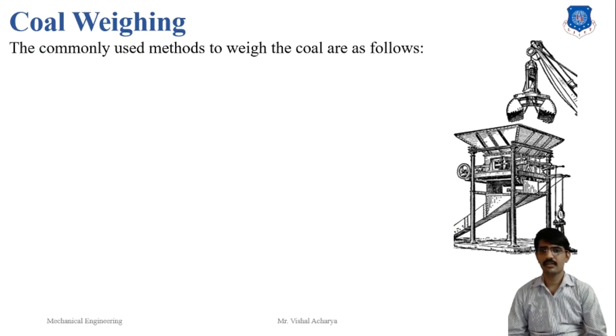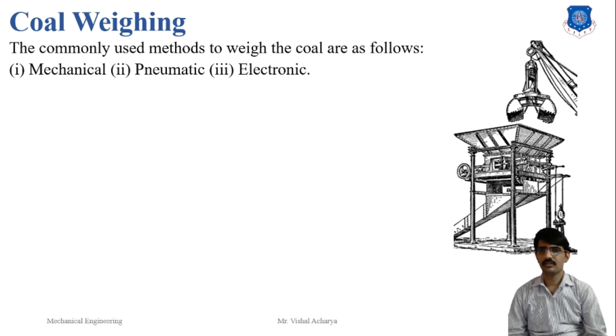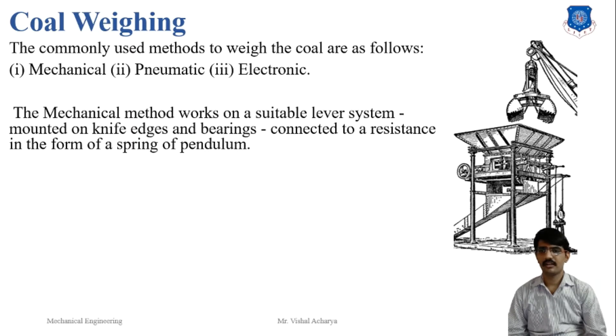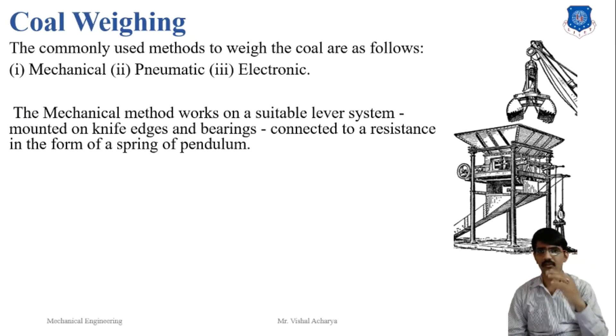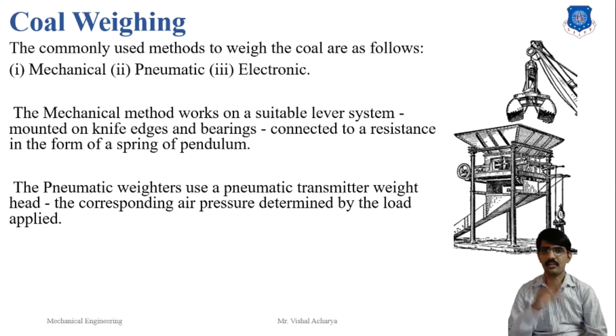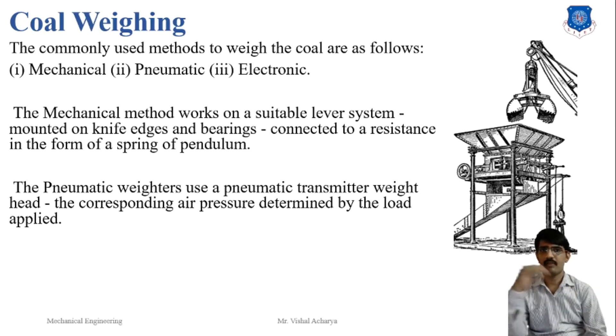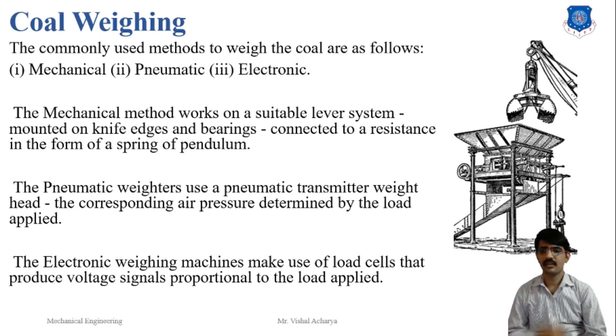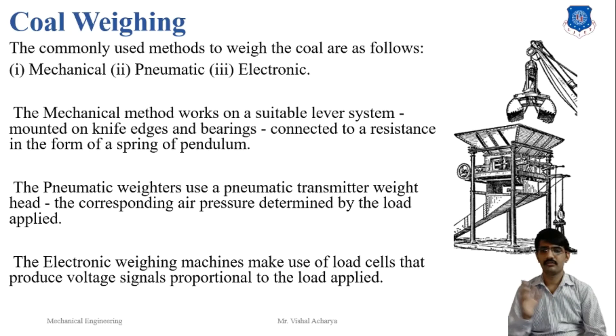Coal weighing is the commonly used method to check the quantity of coal before entering the boiler. Three systems are used: mechanical, pneumatic, and electronic. The mechanical method works on a suitable lever system mounted on knife edges and bearings, connected to a resistance in the form of a spring or pendulum. The pneumatic weigher uses a pneumatic transmitter weight head; the corresponding air pressure is determined by the load applied calibration. The electronic weighing machine uses a load cell that produces a voltage signal proportional to the load applied.